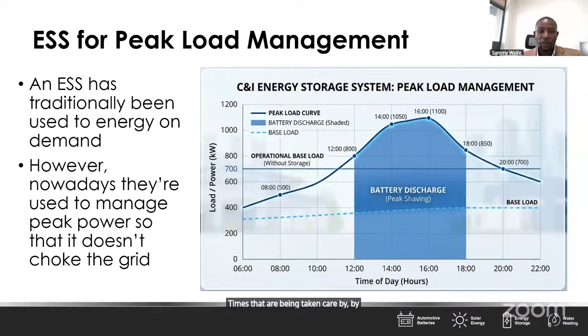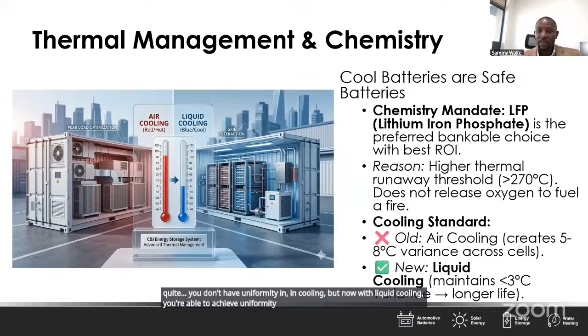When it comes to liquid cooling, the most important thing is efficiency in cooling. It's no longer just about having hotspots, because with air cooling you don't get uniformity, but now with liquid cooling you're able to achieve uniformity across the cells depending on location.